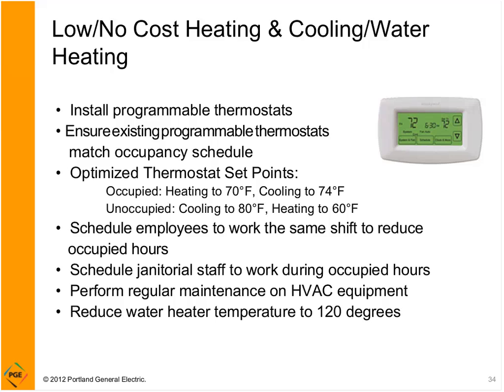We'll move on to low and no cost measures for heating, cooling, and water heating. A relatively low cost improvement would be installing programmable thermostats and making sure that they're set on schedule. There are still a lot of manual thermostats, and sometimes they don't get set back nights and weekends. If you have a programmable thermostat, you're ensuring that a schedule is adhered to, and you're maximizing savings with a pretty low-level investment. Ensure that existing programmable thermostats match the occupancy schedule, daylight savings, or changes in the schedule due to hours worked and so on.